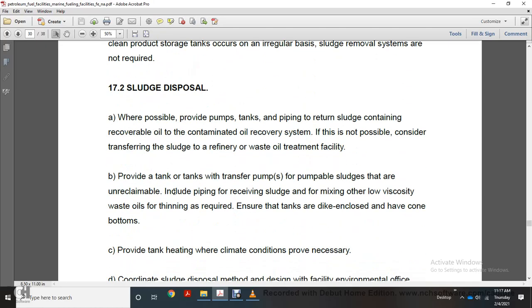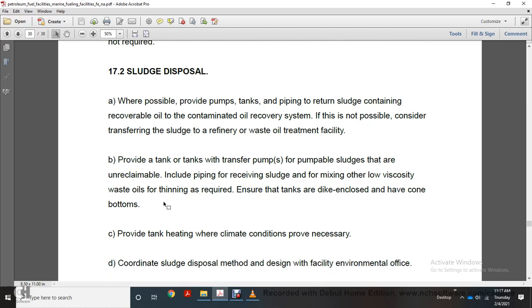Sludge disposal. When possible, provide pumps, tanks, and piping to return sludge containing recoverable oil to a contaminated oil recovery system. If this is not possible, consider transferring the sludge to a refinery waste oil treatment facility. Provide a tank with a transfer pump for pumpable sludge that is unreclaimable, including piping for receiving sludge and mixing in low viscosity waste oil for thinning as required.